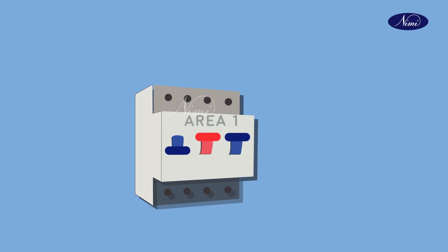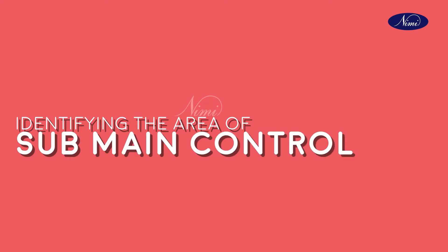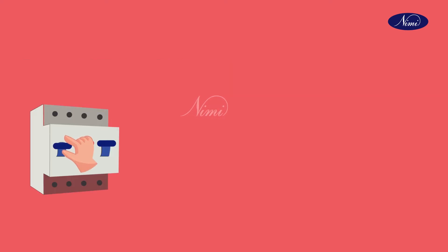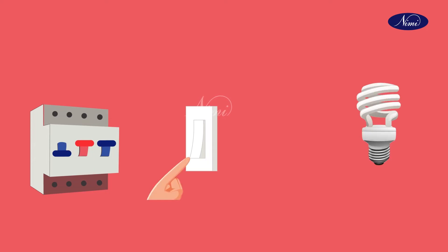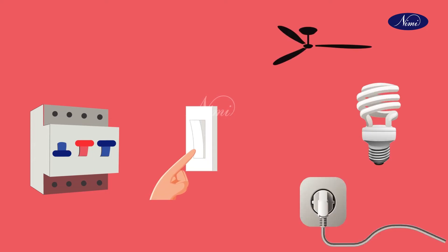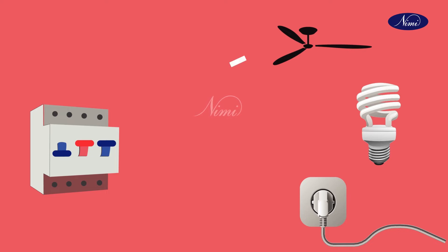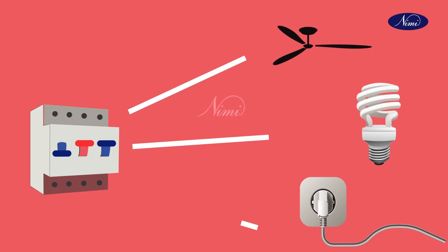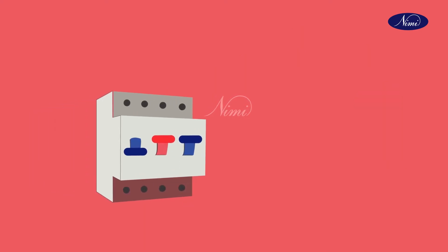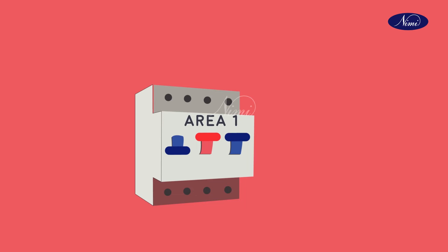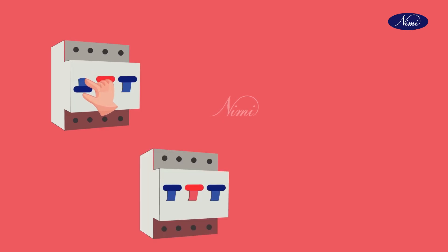If the area is not marked, then it has to be marked. To ascertain the area of sub-main control, switch off one of the sub-main switches and try to switch on the lights, fans and power points in that suspected area. If they do not work, we can conclude that the area covered by those fans, lights and power points is controlled by the sub-main switch which we switched off. Mark the area of control on the sub-main switch. Similarly, one after another switch off the sub-main switches and locate the area of control.